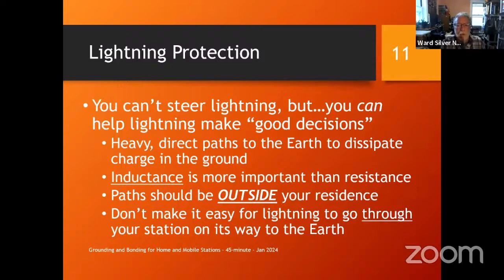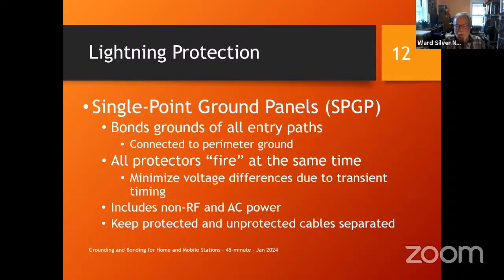Let's talk about single point ground panels. Here's a place where single point is really accurate. The idea for a single point ground panel, usually this is an entry panel for the ham station, is for it to bond all of the entry paths, all of the grounds, together at one spot, very, very close together. Most entry panels are a couple feet by 18 inches or something like that. That's pretty short at most of the ham frequencies that we care about.